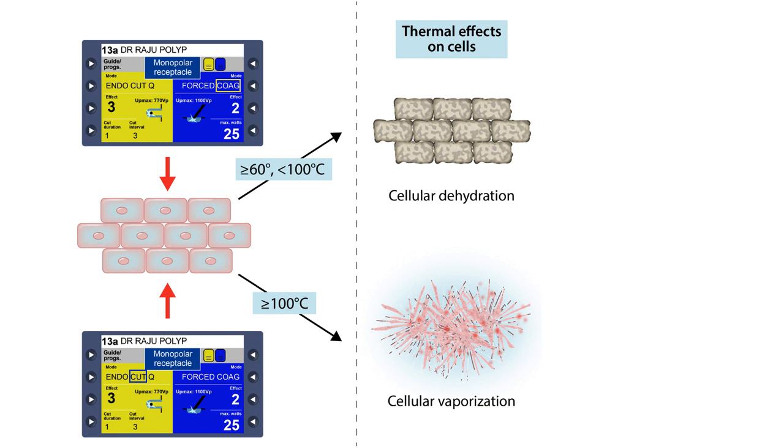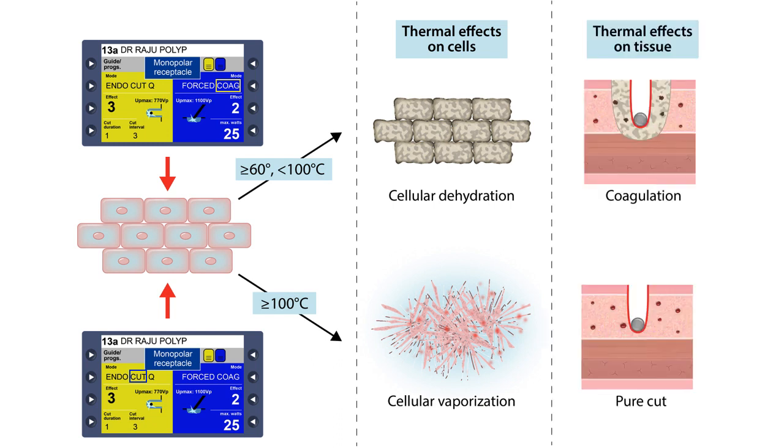With the cut current, the temperature rises above 100 degrees centigrade very fast, resulting in cellular vaporization that ultimately leads to a pure cut. When you use coagulation, the temperature rises slowly to between 60 to 100 degrees, and that slow cooking results in dehydration and coagulation of protein.